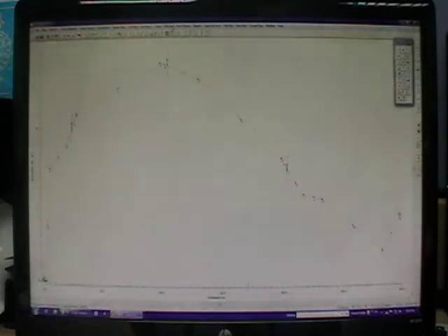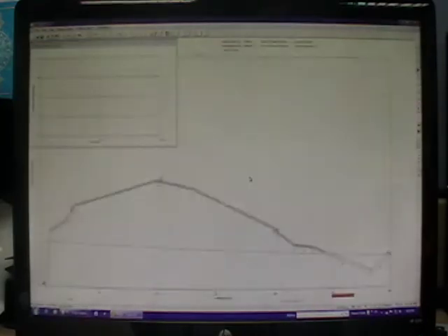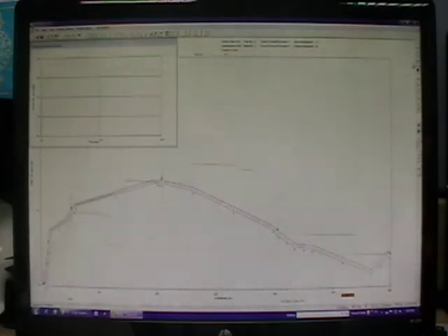And before we look at the results, what we'll do is run an animation of this project to show you the power of animation in analyzing the situation. And here we have the pressure surges going through the system in black. As you can see, it's a complicated situation where the air valves play a role of mitigating the pressures from going all the way down the line.